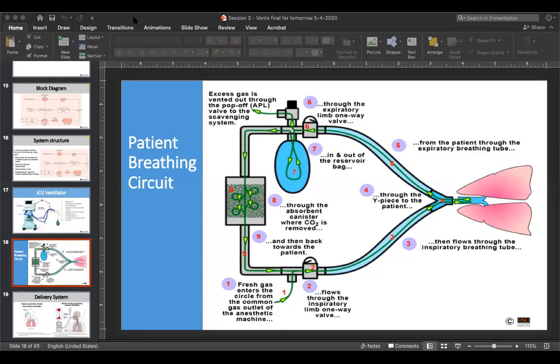So changing the drive gas does not mean you eliminate that gas from being a part of the fresh gas flow, right? So because I change the drive gas from oxygen to air does not mean that I won't have air available as a part of the fresh gas flow to be able to mix that. So absolutely not 100% oxygen to the patient. That will be on an as-needed basis. The concentrations are based on the oxygen levels.